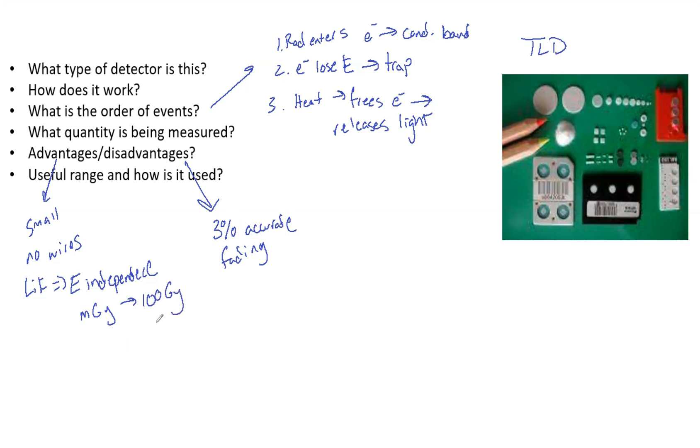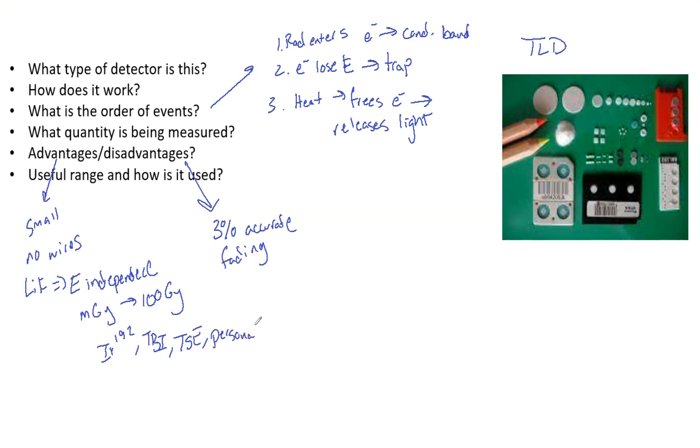The range is milligray to 100 gray, so it has a huge range. You can use it for iridium-192, TBI, TSE, and personal dosimeters. It really does have a lot of advantages and uses in the clinic.